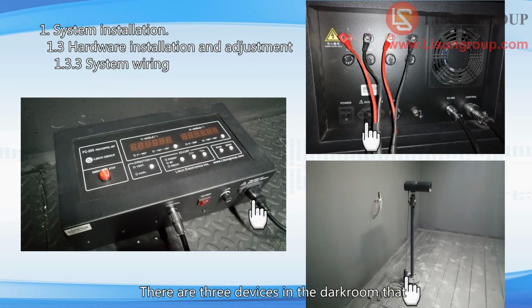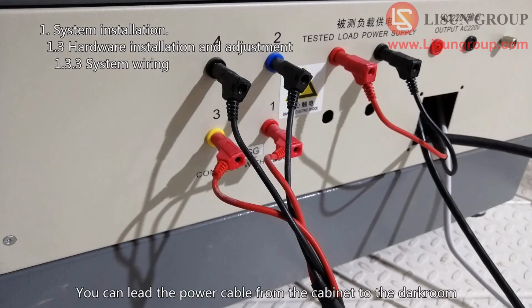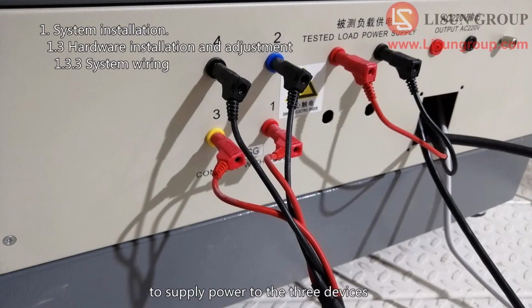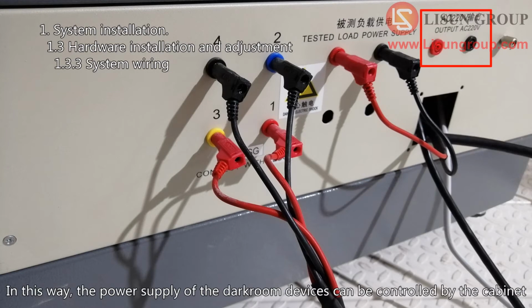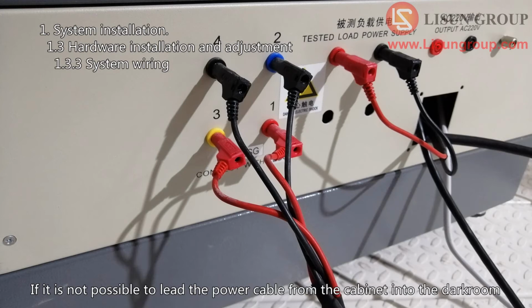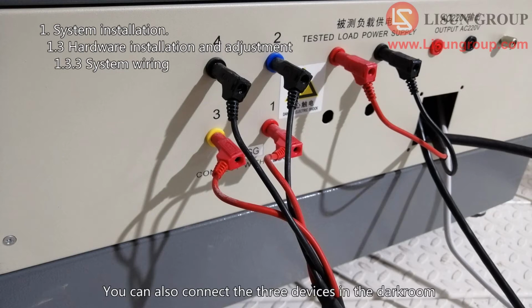There are 3 devices in the darkroom that need to be connected to the power supply: the goniophotometer, the FC200 and the detector. You can lead the power cable from the cabinet to the darkroom to supply power to the 3 devices. In this way, the power supply of the darkroom devices can be controlled by the cabinet. If it is not possible to lead the power cable from the cabinet into the darkroom, you can also connect the 3 devices in the darkroom to the power supply separately.